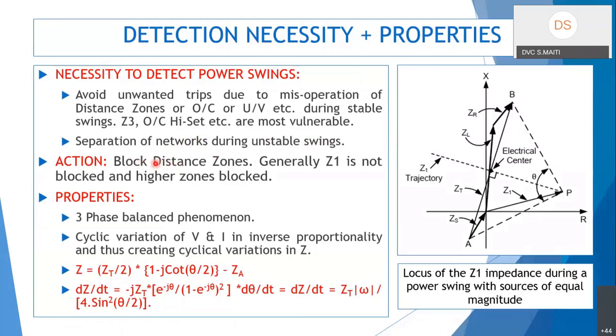The action taken during power swing is to block distance zones. In a typical Indian scenario, zone 1 is not blocked and only higher zones are blocked. Zone 1 is generally the lowest impedance zone, so the power swing impedance is not expected to enter zone 1. Zone 3 is most affected, so higher zones are deactivated by power swing blocking.